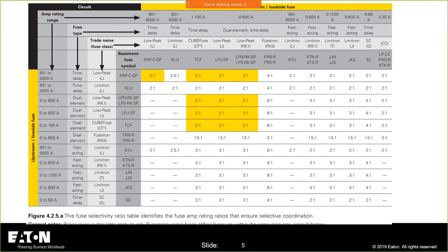These ratio tables, what this means is if I have a downstream fuse and an upstream fuse, as long as, for example, if I have this TCF fuse, 30 amp, downstream of, I don't know, an LPS, as long as I maintain a 2-to-1 ratio. So if I have a 30 amp TCF downstream of anything that is 60 amps or more, I maintain selective coordination for all currents up to 200,000 amps that flow through them. So as long as I have a 30 amp downstream of a 60 amp or greater, I maintain a 2-to-1 ratio.